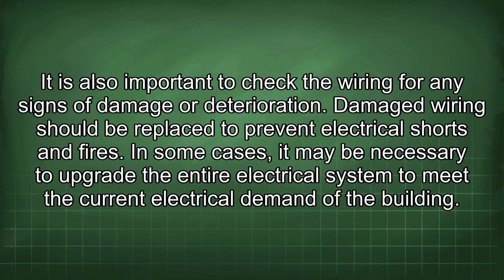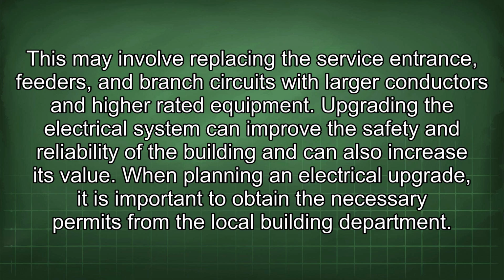In some cases, it may be necessary to upgrade the entire electrical system to meet the current electrical demand of the building. This may involve replacing the service entrance, feeders, and branch circuits with larger conductors and higher rated equipment. Upgrading the electrical system can improve the safety and reliability of the building and can also increase its value.